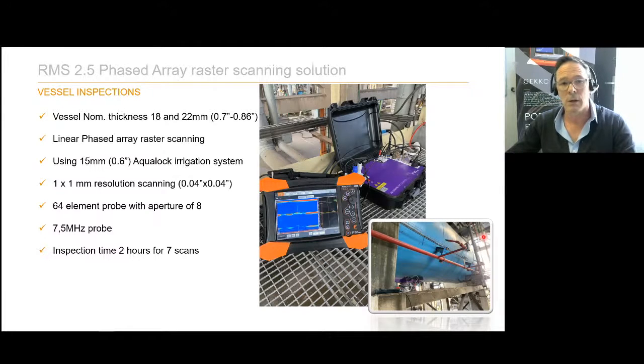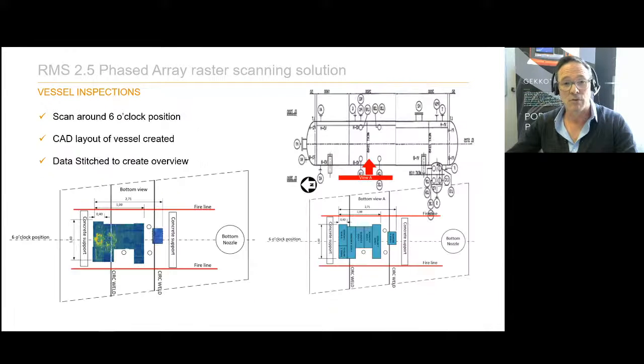Using a 1x1 configuration pitch with a 64 element probe and an aperture of 8 with a 7.5 megahertz. And the whole scan of this tank bottom, not whole, but the section that we could reach, we've done 7 scans in 2 hours. So that's quite productive for a unit. And doing this by hand, you would get less good data, and obviously probably take you quite a bit longer. And also the reporting would be quite a bit more difficult.